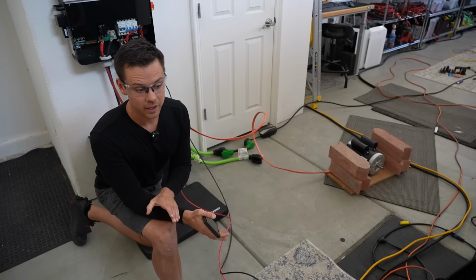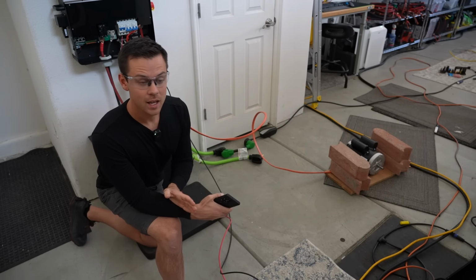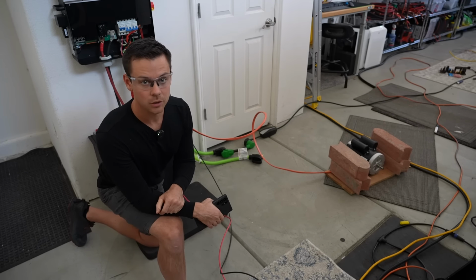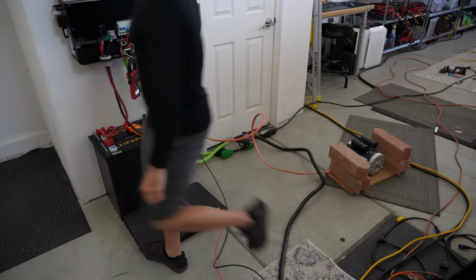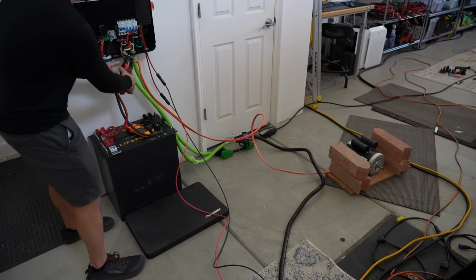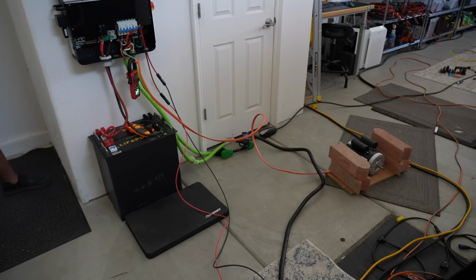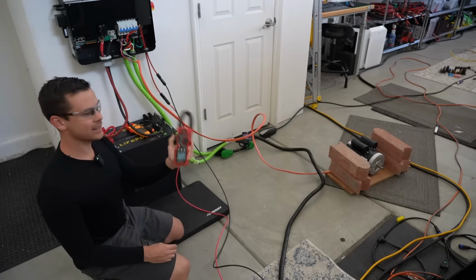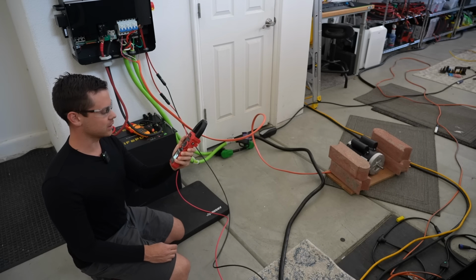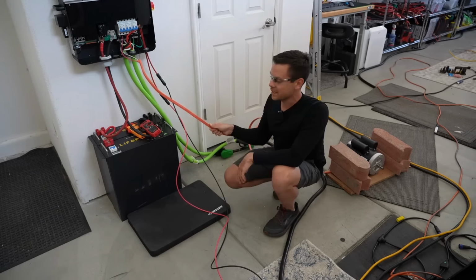Now, if the inverter circuit can't do it, let's see if the grid can. That will tell me if I wired it incorrectly or something else. So here's the grid connection, and we can measure the inrush and see what we need. Woo! 300 amps? Yeah, it's either improperly wired or something else is going on. That is ridiculous. Man, I don't like this motor.